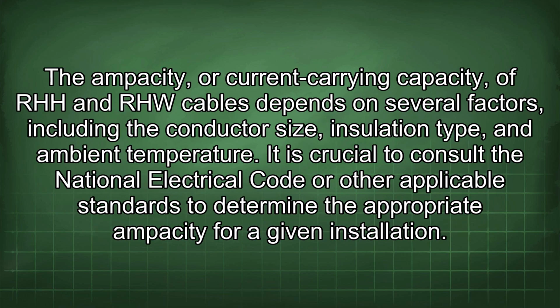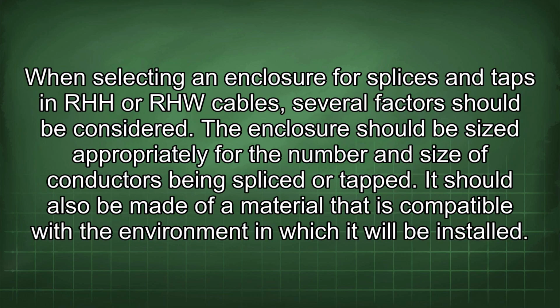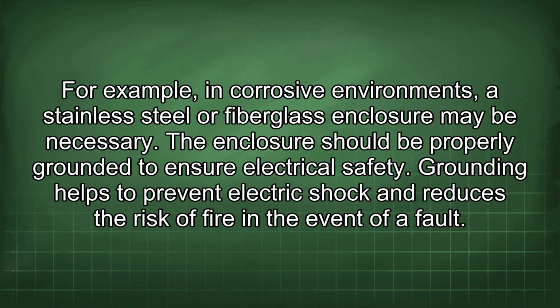The ampacity, or current carrying capacity, of RHH and RHW cables depends on several factors, including the conductor size, insulation type, and ambient temperature. It is crucial to consult the National Electrical Code or other applicable standards to determine the appropriate ampacity for a given installation. When selecting an enclosure for splices and taps in RHH or RHW cables, several factors should be considered. The enclosure should be sized appropriately for the number and size of conductors being spliced or tapped. It should also be made of a material that is compatible with the environment in which it will be installed. For example, in corrosive environments, a stainless steel or fiberglass enclosure may be necessary. The enclosure should be properly grounded to ensure electrical safety.